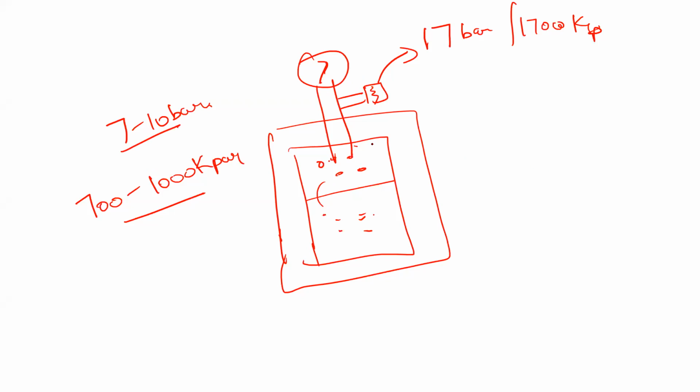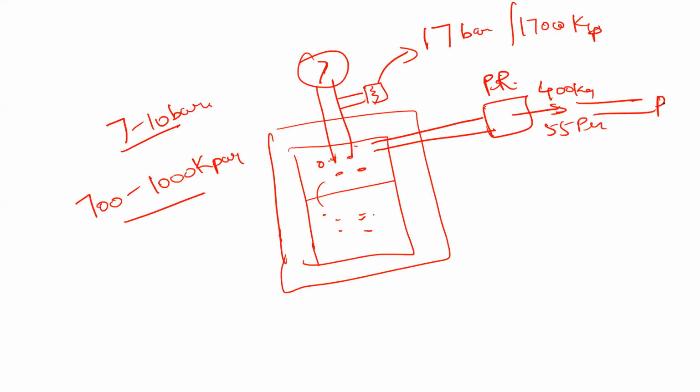Right. Now we are going to utilize the vapors for the hospital purpose. Then you've got the pressure regulator. This will reduce the pressure from 700 to 1000 kilopascal to the intermediate pressure system, which is 400 kilopascal or 55 psi, and then it goes to the hospital pipeline. There is another one called the control valve.